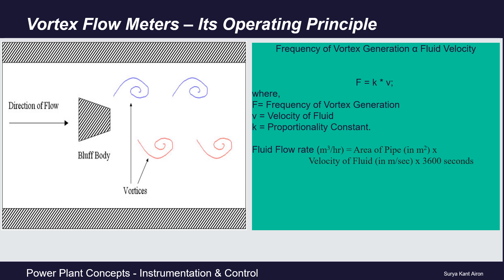Coming to its operating principle: whenever an obstacle is placed in a flowing fluid path, vortices are generated alternately on both sides of the obstacle — shown here in blue and red. The frequency of vortex generation is directly proportional to the fluid velocity and is independent of all other parameters. That is: frequency F = K × velocity V.